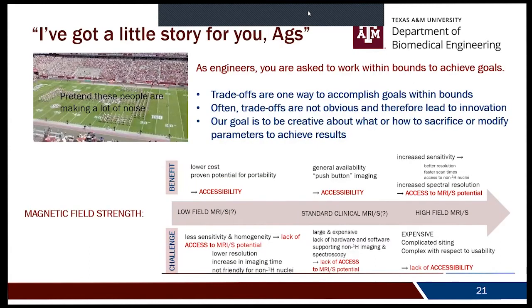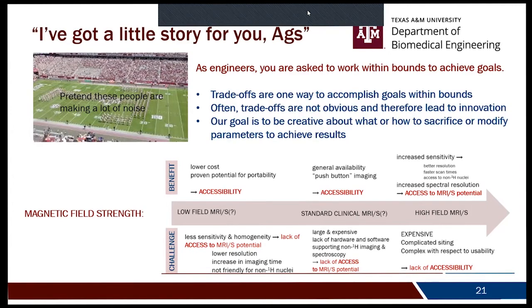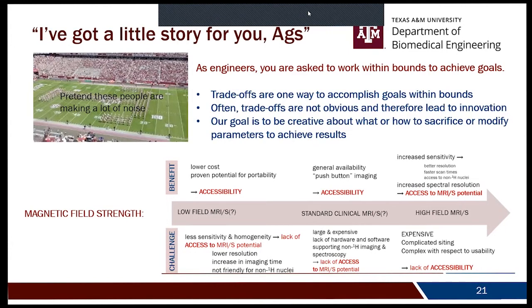Trade-offs are one way that can lead to innovation. We don't have to invent something brand new — we can manage trade-offs in our design. Our goal is to be creative about what you can sacrifice and how you can compensate. With magnetic field strength and MRI: you've got low fields, standard clinical fields, and high fields. Low field gives lower cost and proven potential for portability, but less sensitivity and less field homogeneity — less access to MRI's potential but more access to the equipment.